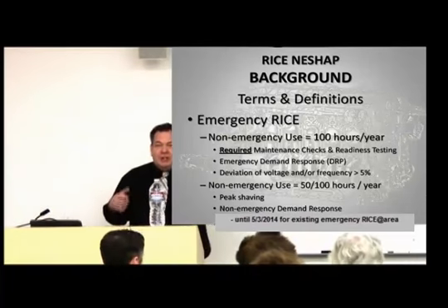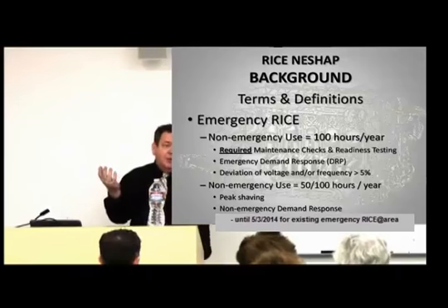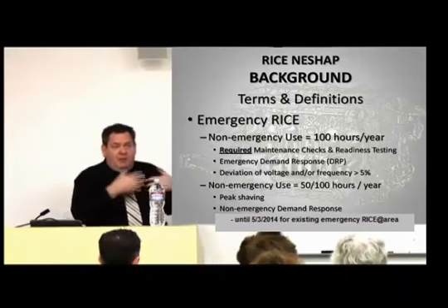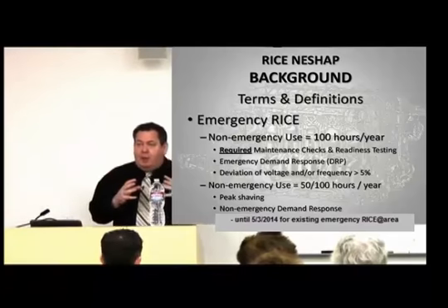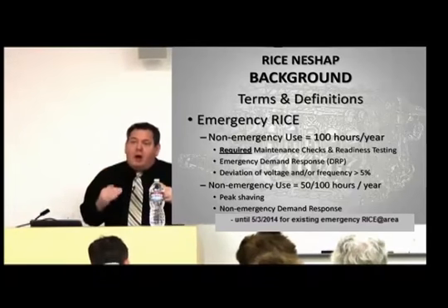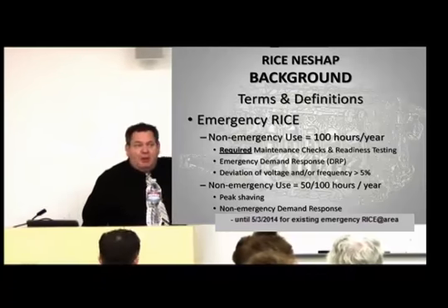And this is a recent change in the rule to harmonize it with our ATCM, at least relative to the compression ignited engines, but this change in the rule affects all engines. And what the change in the rule is that you're allowed to operate your engine up to a maximum of 100 hours per year for any combination of these 3 reasons.